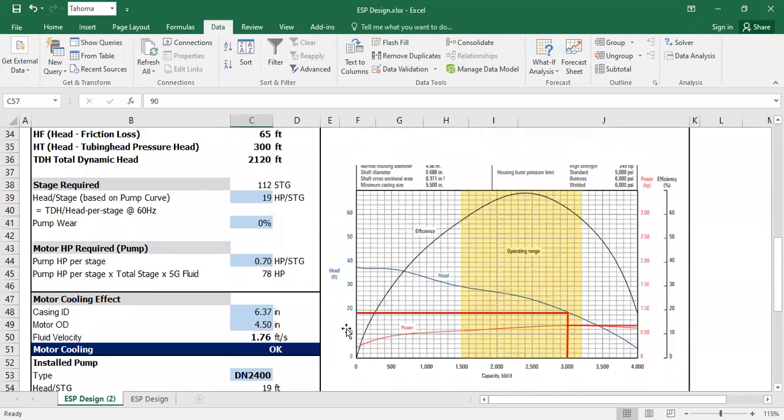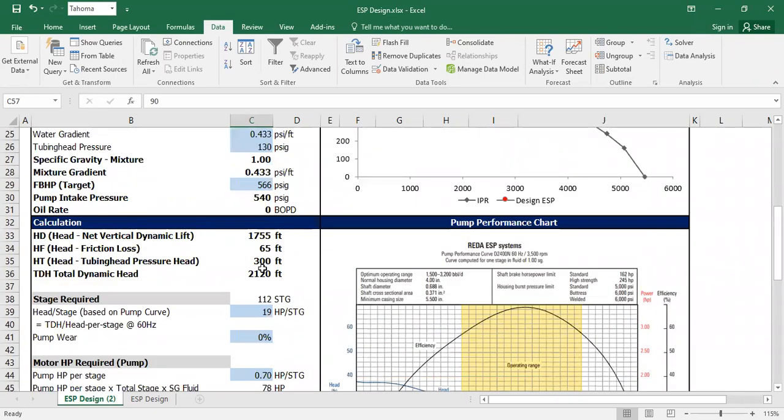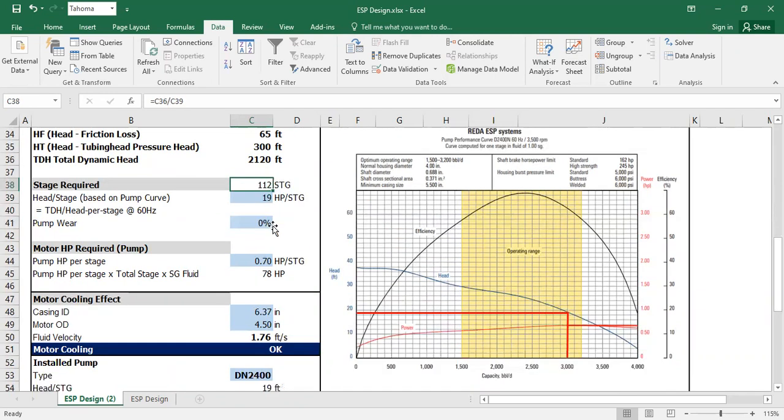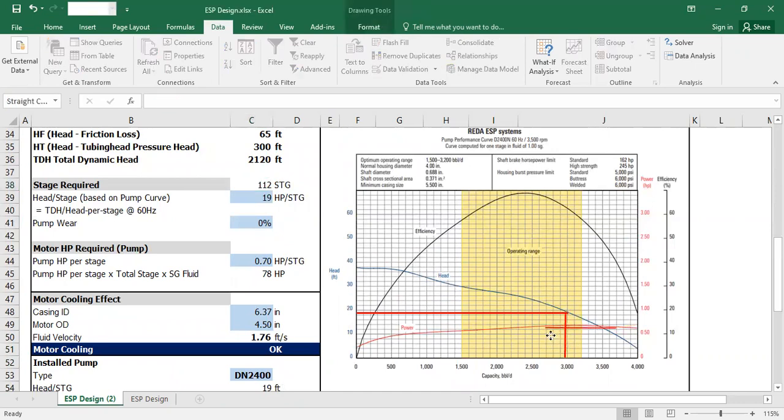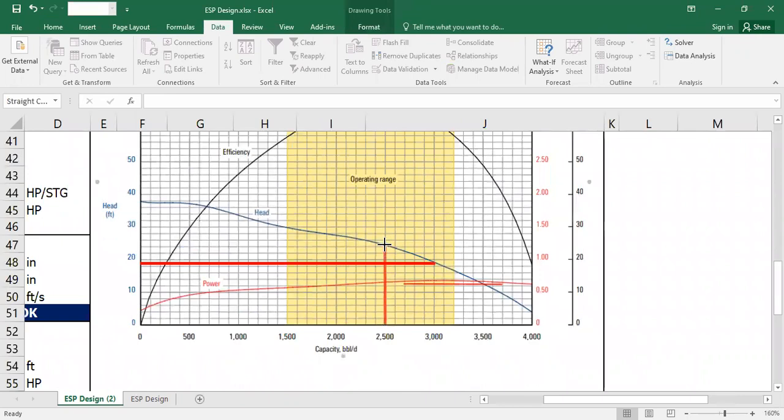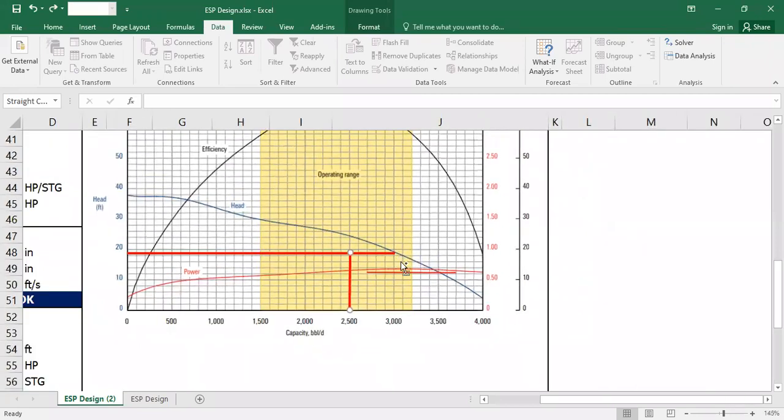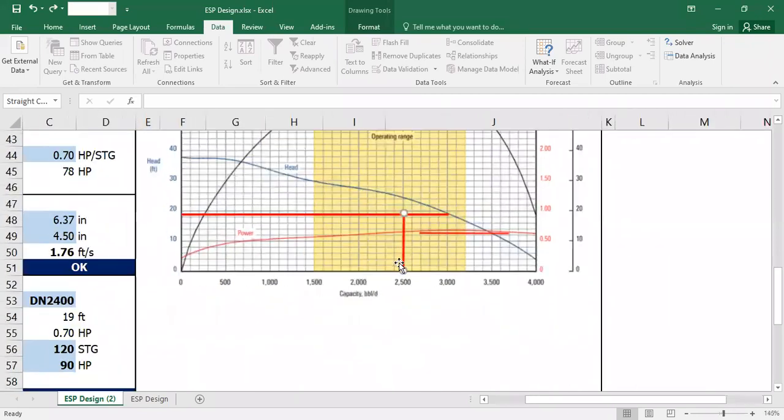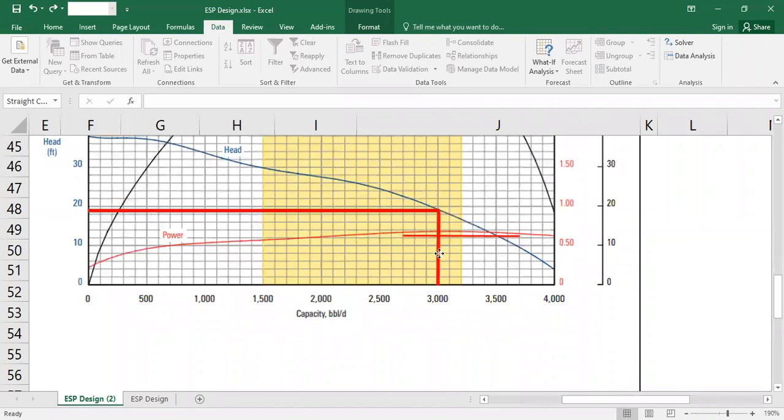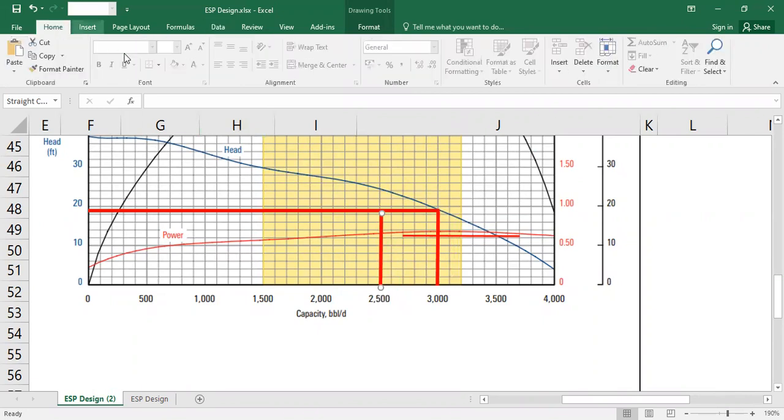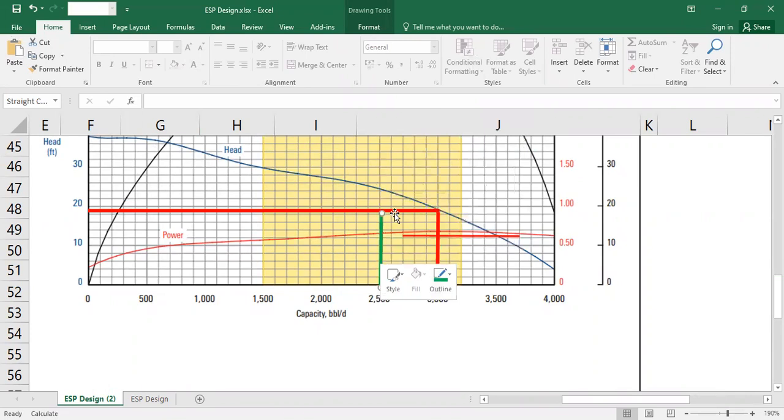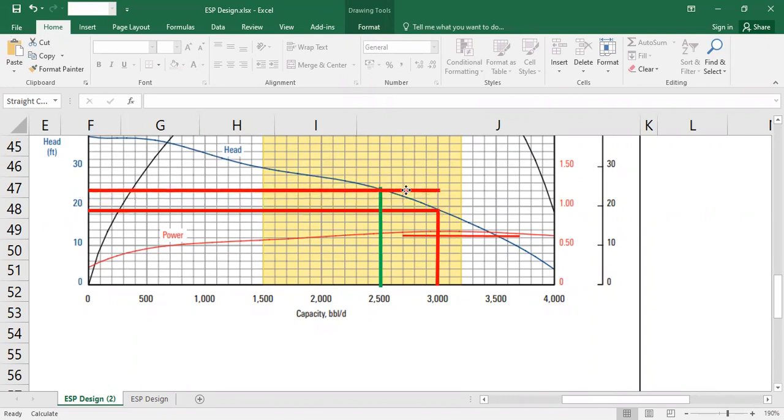I already reduced the dynamic head and thus reduced the stage required, and I also need to adjust this to 2500. Okay good, 2500 still in optimum operation. I put it here, I copy another line, I color it green instead. But it's at 2500, and there you go.